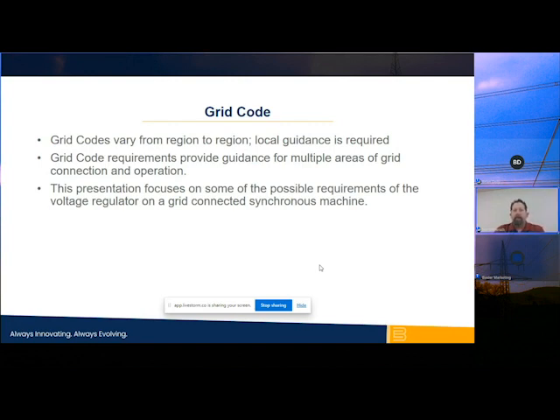Grid codes are going to provide the requirements and the guidance for multiple areas of grid code connection and operation. So it's not just the voltage regulator, even though that is my focus of the talk today. It's really about how the voltage regulator fits into the grid codes. The grid codes are basically going to give guidance for anything that's going to be connected to the grid, removed from the grid, how they're going to connect, anything that's going to provide power. All those different areas and how they interact are covered by those grid codes. So today with this presentation, we're focusing on the voltage regulator and how it contributes to grid connected synchronous machines. We're just going to talk about a little piece of the grid codes in reference to the voltage regulator.